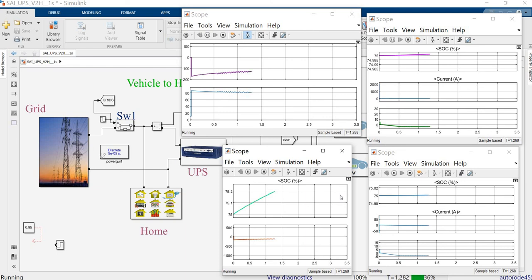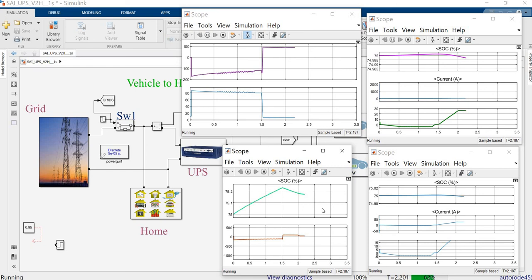At a specific point, the grid is disconnected. After disconnecting, the energy is transferred from the battery to the load. The current flow changes from negative to positive. Up to 75.2, the SOC was maintained. After that point, we are drawing current from the EV — the current from the EV is flowing into the system.